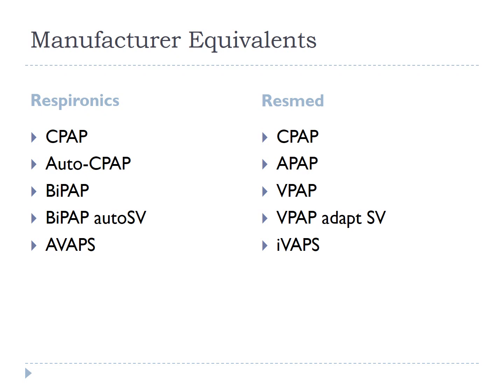Next, we have what's called an auto-titrating bilevel therapy. These machines have two pressures, an IPAP and an EPAP, and they adjust to the patient's breathing pattern automatically. These adjustments in pressure are called pressure support, and the machine makes these adjustments by measuring the breath-to-breath peak flow. As it measures the breath-to-breath peak flow, the machine averages out the peak flow according to the last 4 breaths taken. The machine then adjusts the pressure on the average of those last 4 breaths. In these modes, the machine is trying to continue a normal peak flow by adjusting both variable pressures and the overall pressure support level. Respironics calls this machine a BiPAP Auto SV. ResMed calls this machine a VPAP Adapt SV.